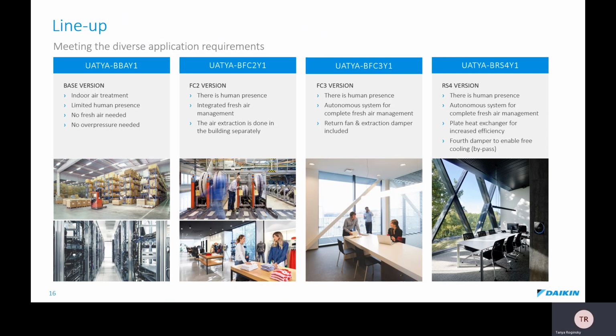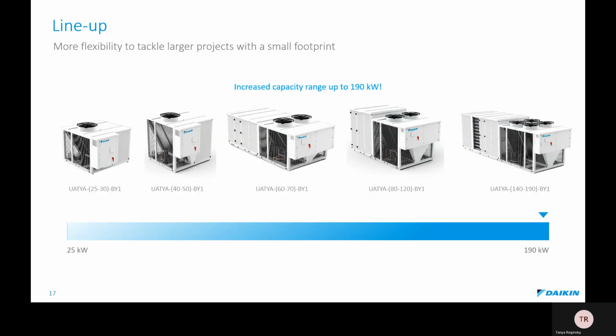The fourth and completely new version is the RS4 series, which offers heat recovery with the cross-flow heat exchanger. This is a 4-damper arrangement. This is the most advanced and most energy-efficient solution. Cross-contamination of airflow is not possible thanks to the design of the cross-flow heat exchanger. And the application would be similar to the FC3 series. The capacity ranges from 25 kilowatts up to 190 kilowatts.